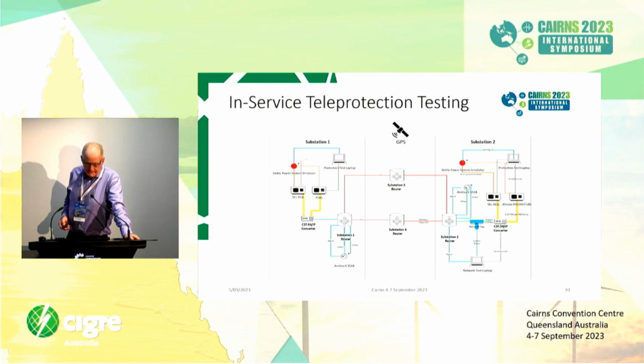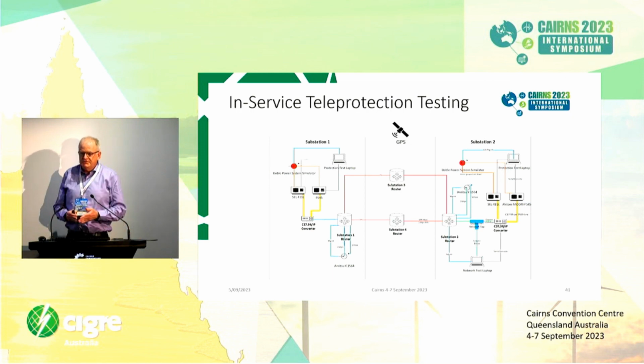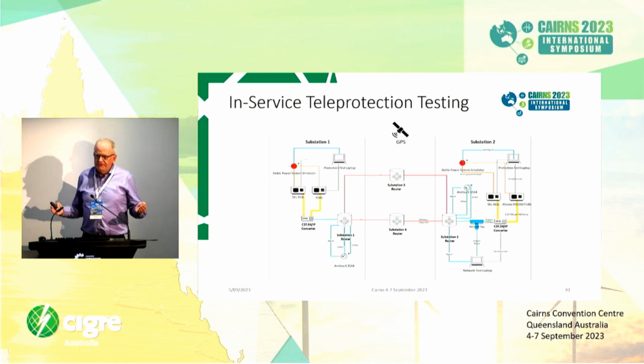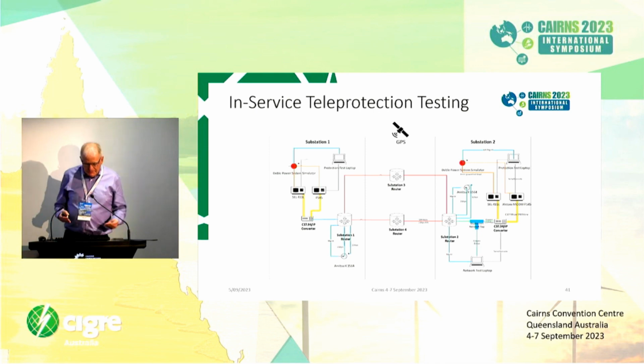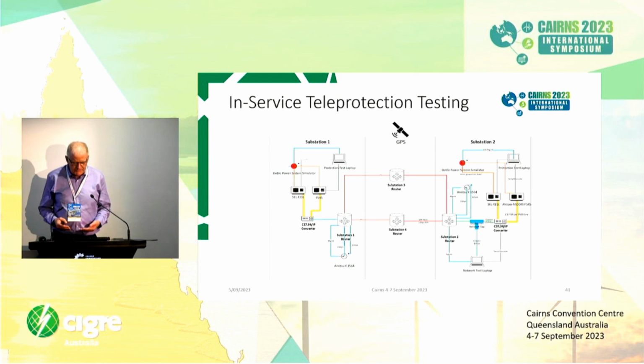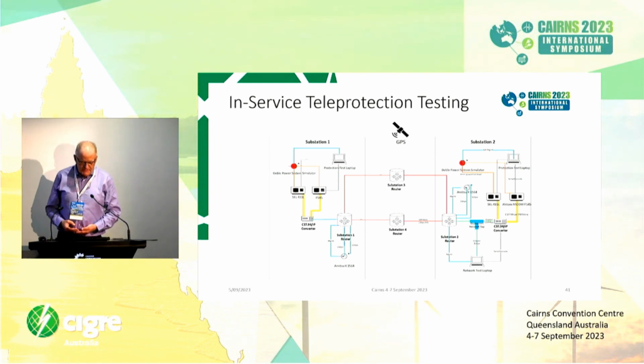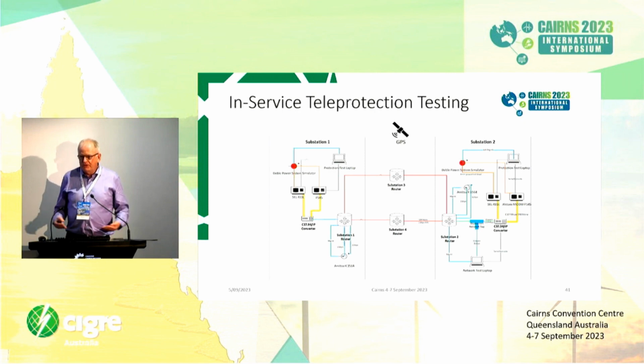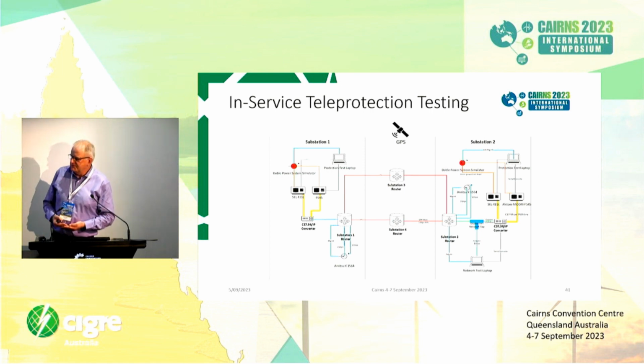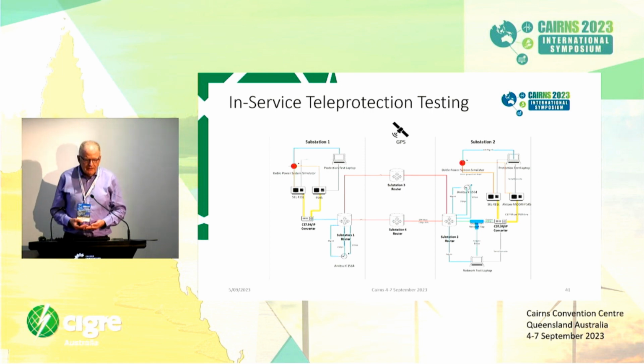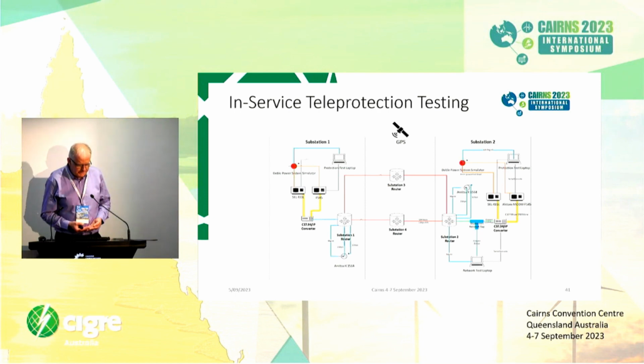Okay, so obviously we're looking at a hugely complex system here. You've got protection relays talking to C37.94 to IP converters. Then you've got the MPLS network itself. So you've got to make sure you're testing each component and each system within the network. It's not good enough really just to run tests on the protection system itself during your commissioning.